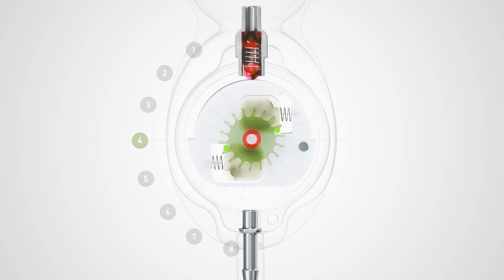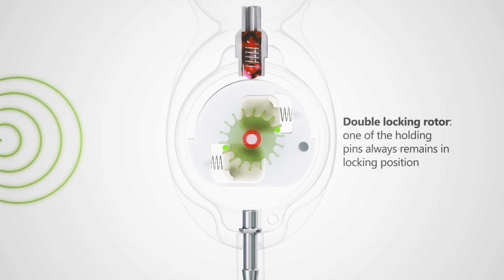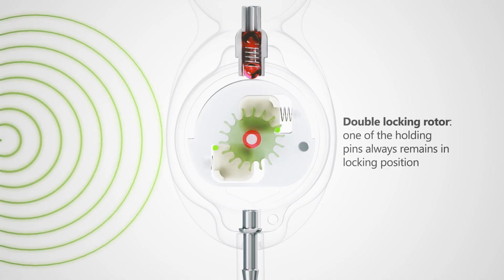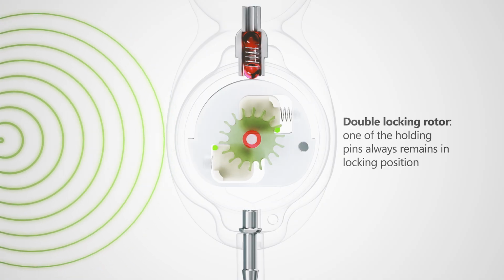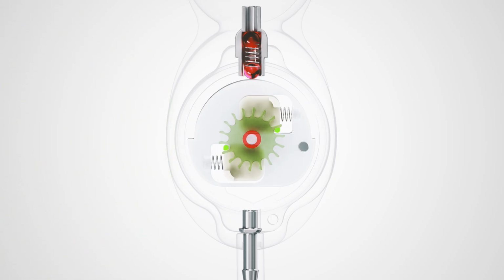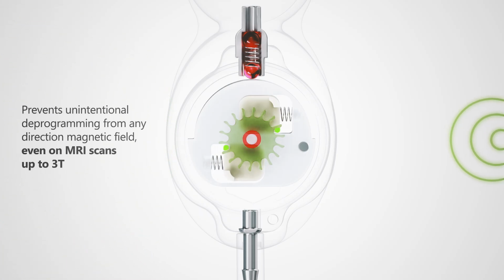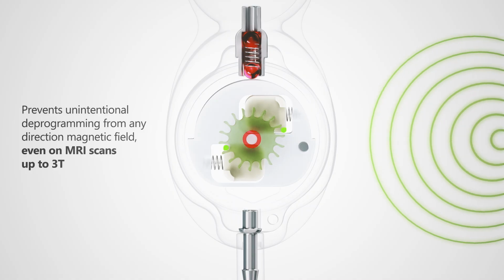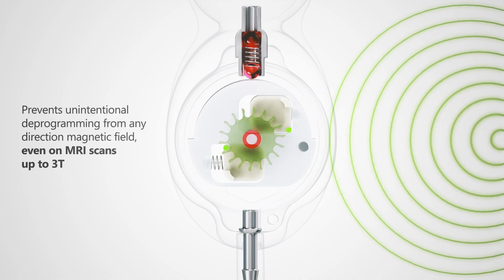The rotor has two magnets with locking pins pressured to the center by coil springs. The action of external magnetic fields from any direction cannot release both locks at the same time. By moving in opposite directions, even when one pin is released, the other is forced to remain in the locked position. This innovative mechanism prevents involuntary deprogramming, even when the patient undergoes MRI examinations of up to 3 Teslas.